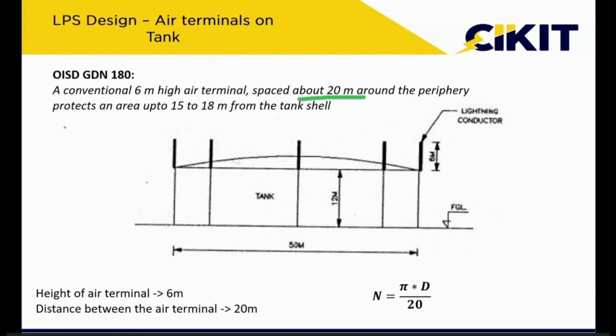So if I am placing one every 20 meters, then the number of air terminals required will be pi d by 20, or 2 pi r by 20. That is the formula which can be used for calculating the number of air terminals. The point we have to note down is that the height of the air terminal has to be 6 meters above the tank, and we have to place them at every 20 meter spacing. So here, if you observe, the diameter of the tank is 50 meters and we are placing air terminals at every 20 meters.